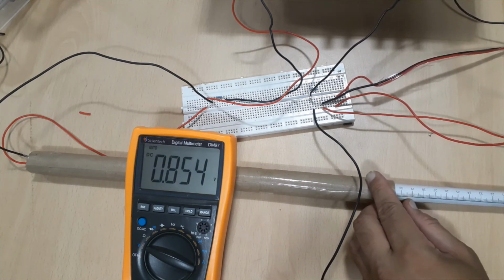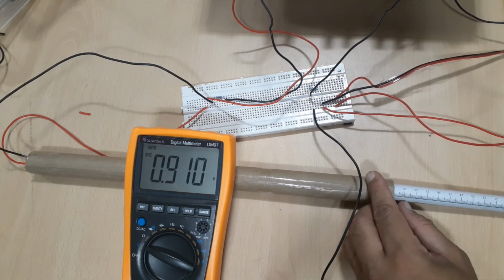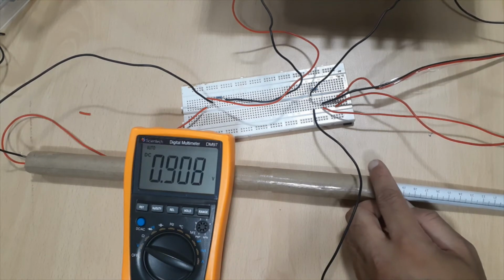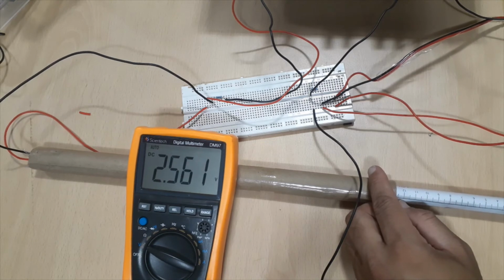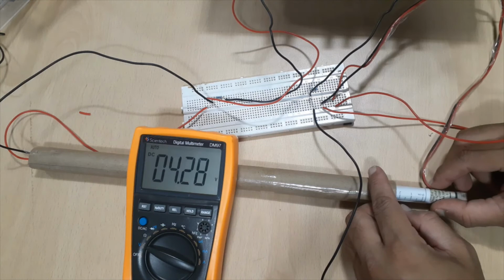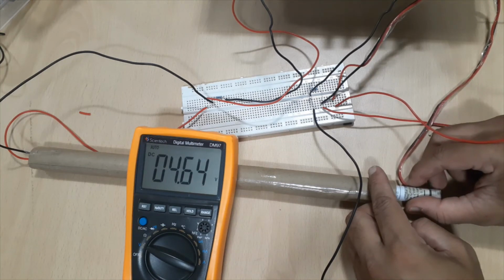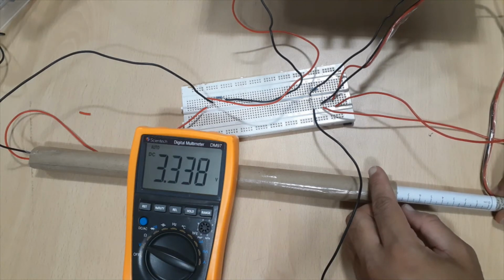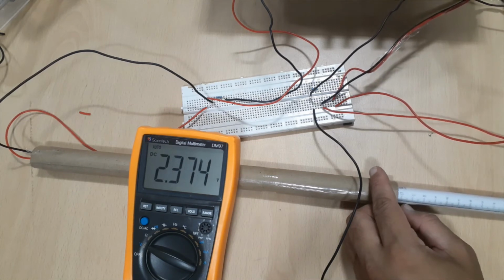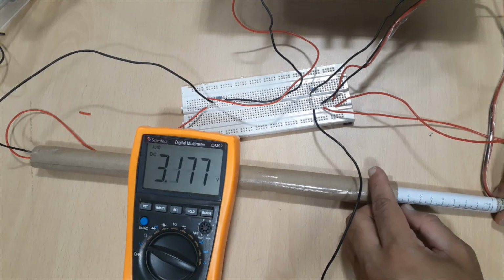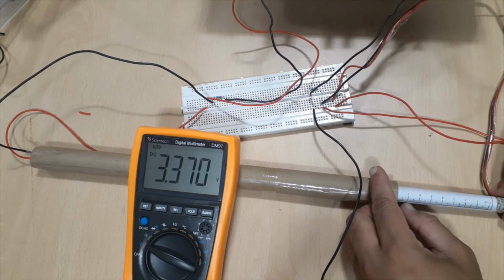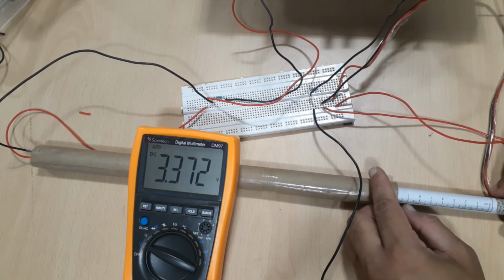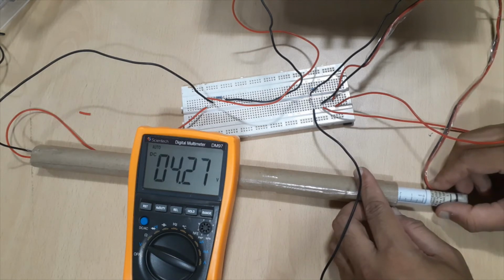This is now at 30 centimeter, 0.9 volt. Let us see first of all, do we get a nice change in voltage which we can utilize for control purpose. At 8 centimeter we are getting 3.3. Let us move it and move back and see whether we get the same or not. Again you get approximately 3.3. Again if you take it out and insert at 8 centimeter, I was checking the repeatability of this one. So repeatability is good. Now let us take the reading from 0 onwards in the reverse way.